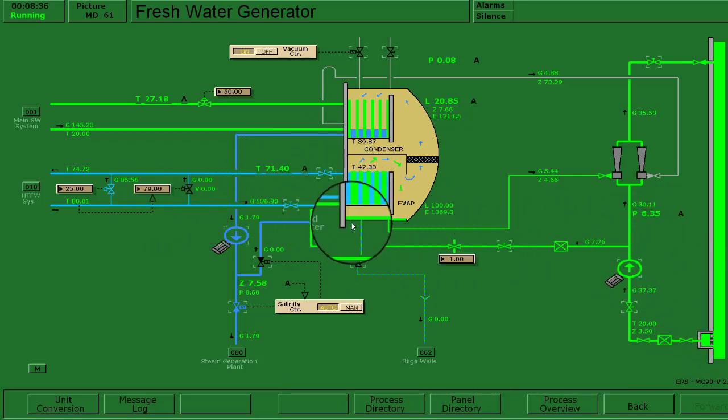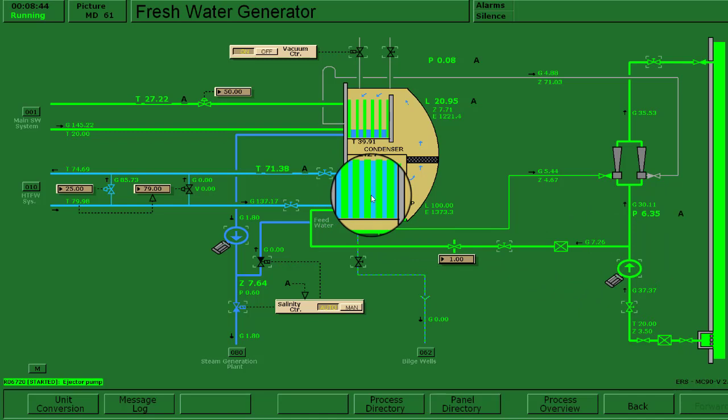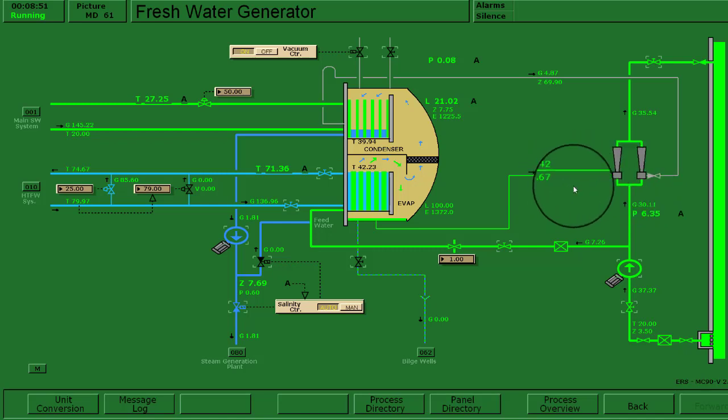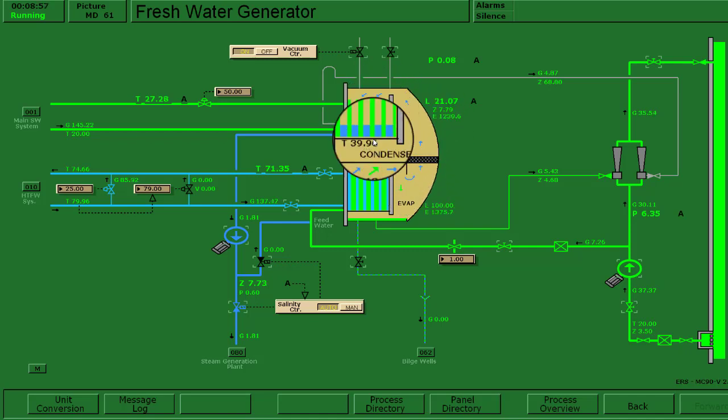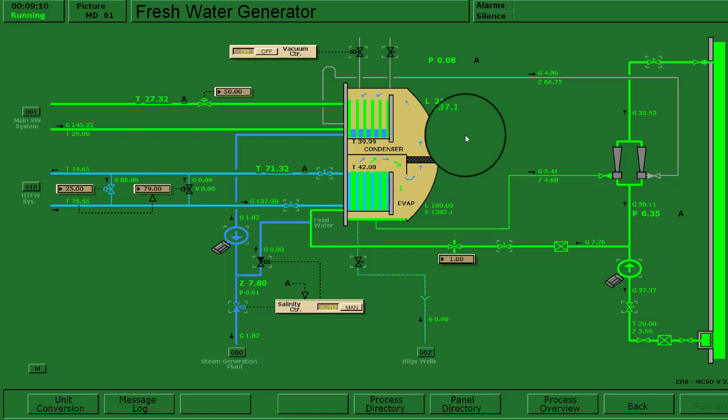Now, since there is water that goes through here from the seawater, of course it evaporates. Now, since the seawater is running through and out through the eductor, of course, with the Venturi effect, it creates vacuum or negative pressure. Now, you have a negative pressure within the shell or inside of the chamber. Basically, as I mentioned in the earlier part of this discussion, the boiling point temperature of a certain liquid goes down or goes up directly proportional with the pressure. So hence, with this condition, the pressure is negative, then the boiling point of water is also very low.